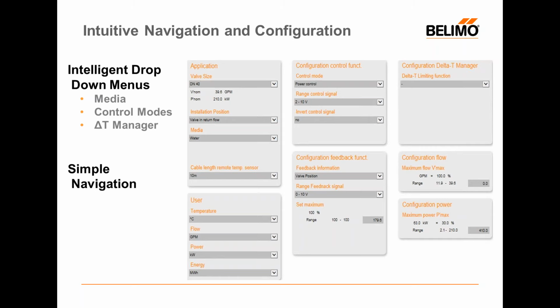Here we can also adjust our input signal, invert the signal if we want to reverse or direct acting control routine. Below that we can configure our feedback, whether you want valve position, flow. We can also do supply or return water temp, delta T, or power. The signal for the feedback can be ranged either 0 to 10, 2 to 10, 0.5 to 10.